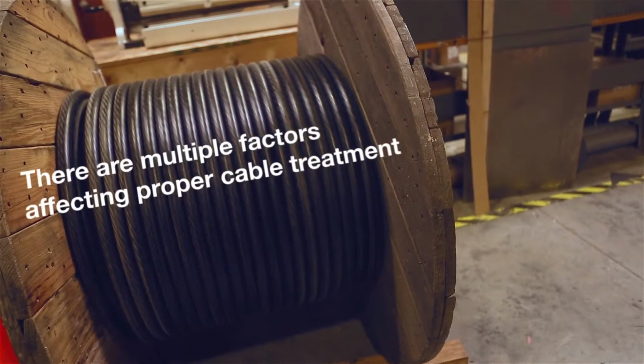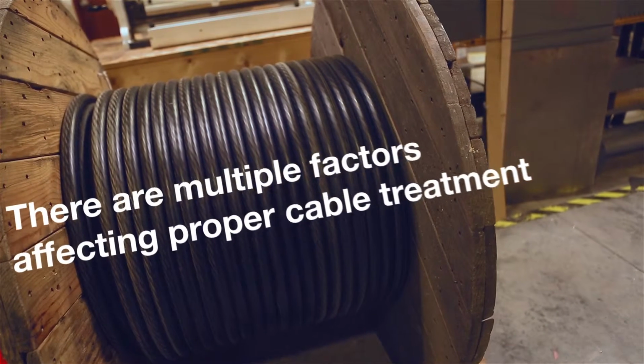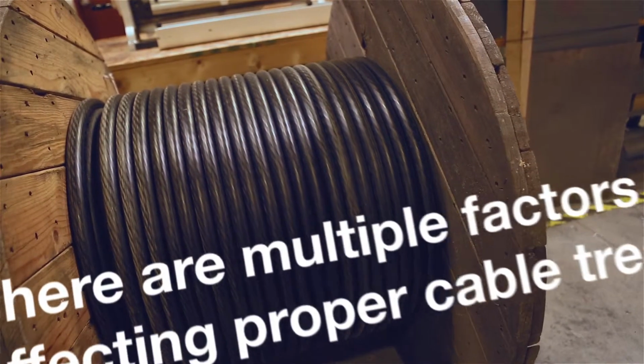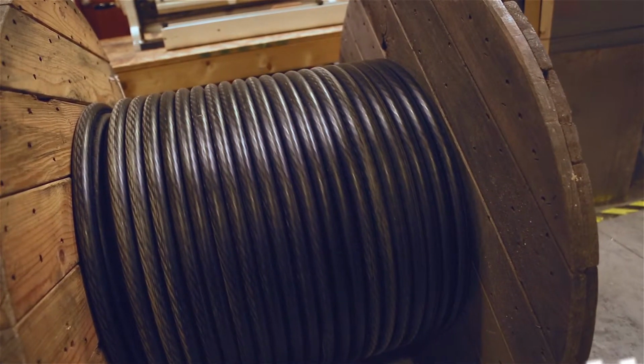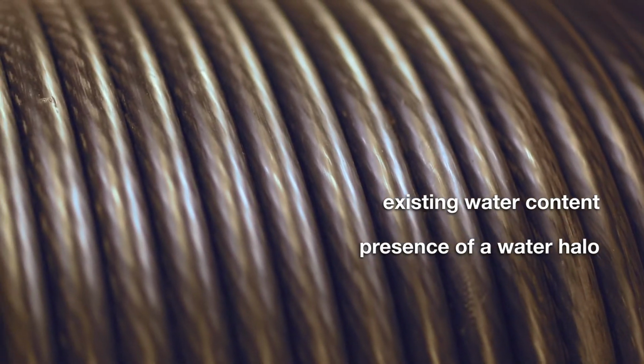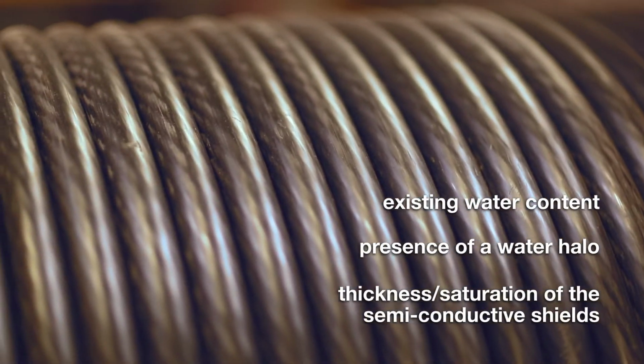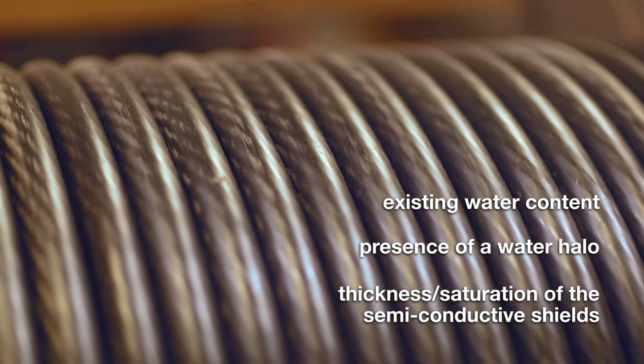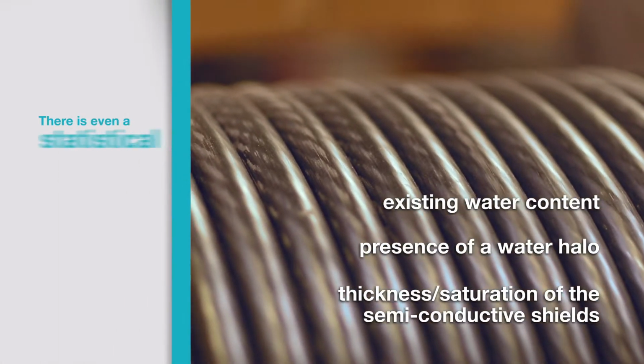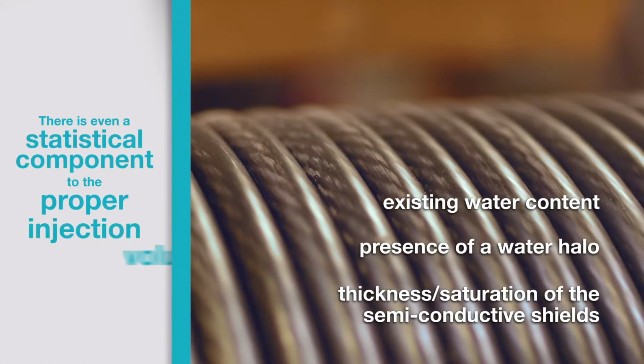This is important, as there are multiple factors that affect the optimum amount of fluid required to properly treat a cable's insulation. Some of these factors include the existing water content in the cable's insulation, the presence of a water halo, and the thickness and saturation level of the cable's two semiconductive shields. There is even a statistical component to the proper injection volume.